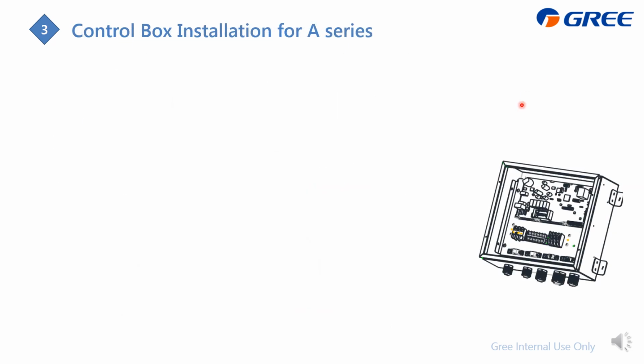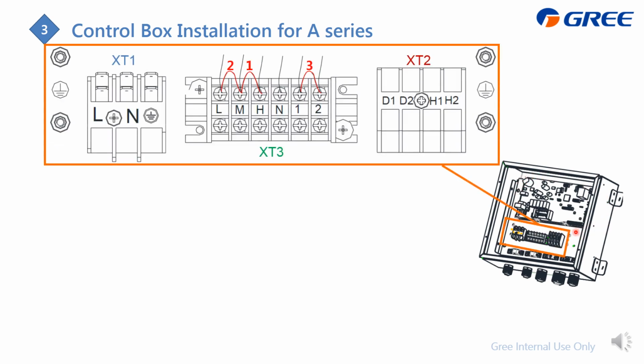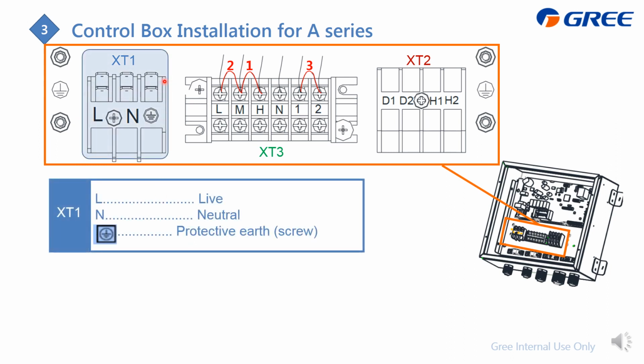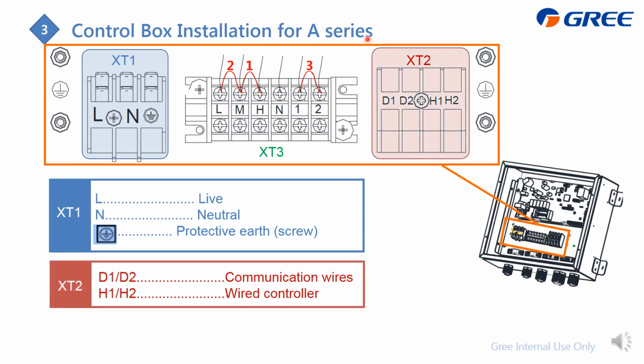Next is for the detail wiring. First is for the A series. And here is the control box. Inside there is a control PCB. This is the terminals, which is this part 1. And from here you will find that this XT1 is for the power supply, is single phase. And the XT2 is for the communication. D1, D2 for the communication with outdoor unit or next indoor unit. And H1, H2 is for the wire controller.